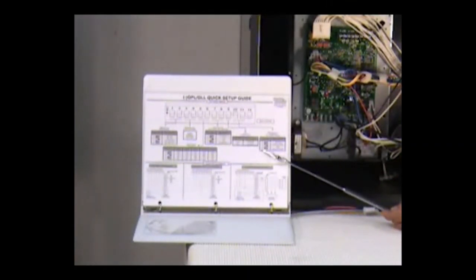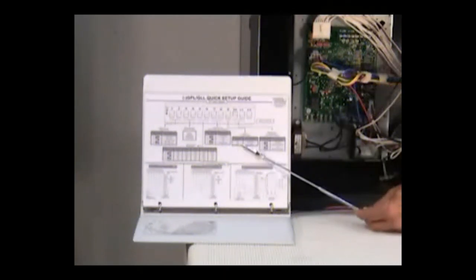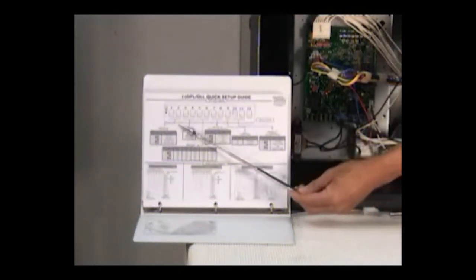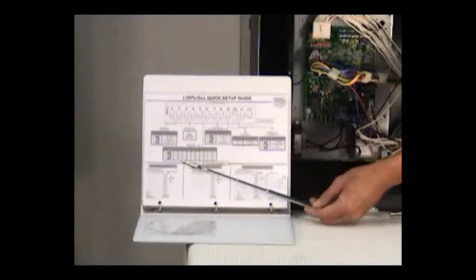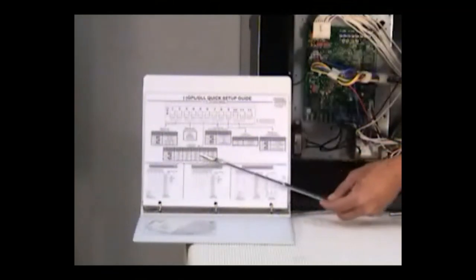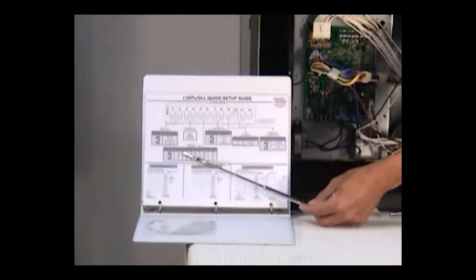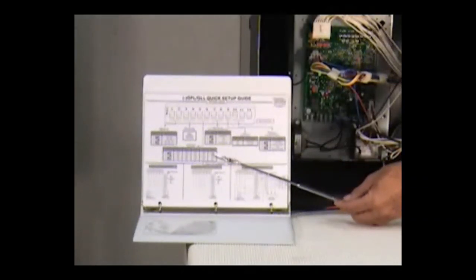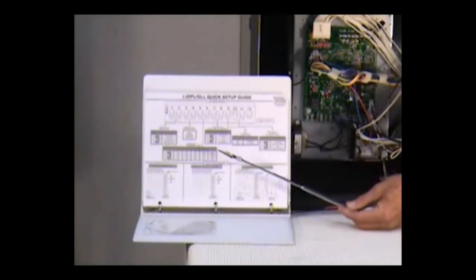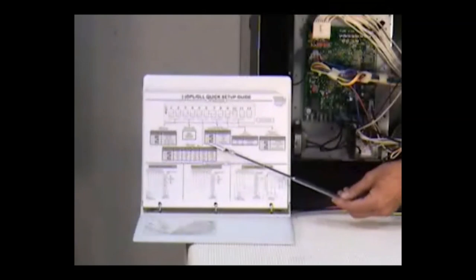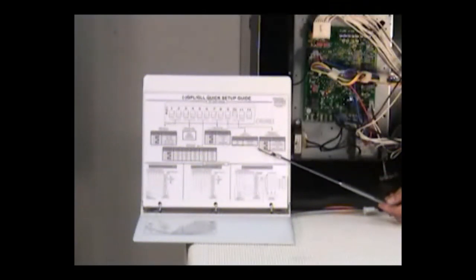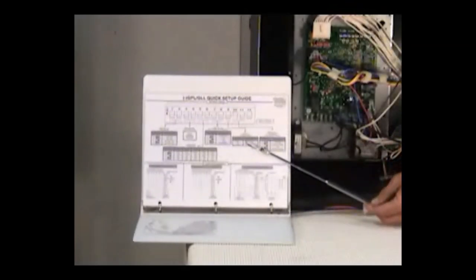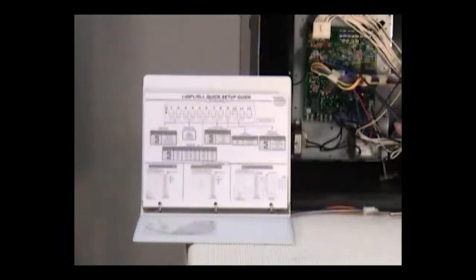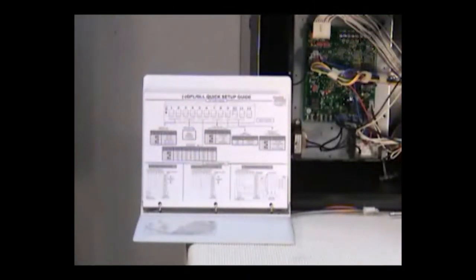The recommendation is that you use the specific manufacturer's installation and operation instructions so that you can determine how you need to set the speeds, like in this graph right here. This one here is telling us what speed we need as far as CFM. And that set of switches there will determine whether we're dealing with a 3-ton, 3.5, 4, or 5, could be even lower than that, or up through to the 2,000 CFM of air. And each manufacturer does it slightly different, and so you can't explain each and every one through one graphic like this. This would be specific to this manufacturer.